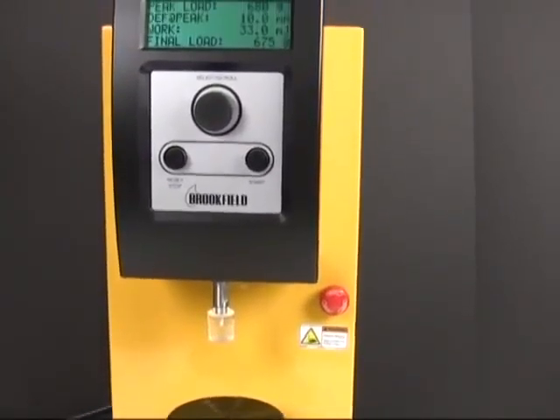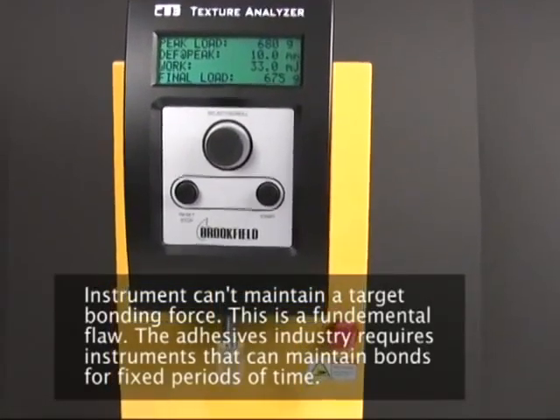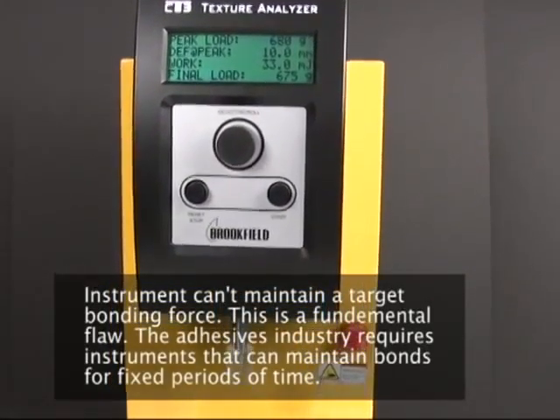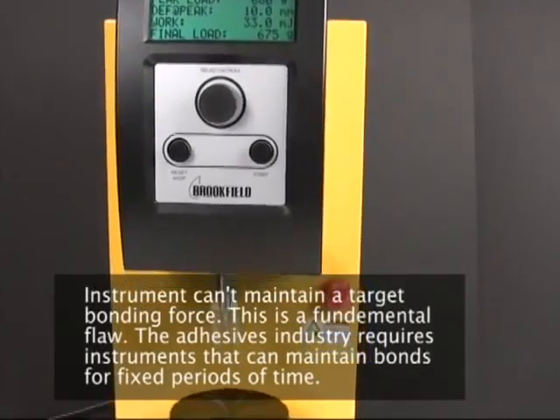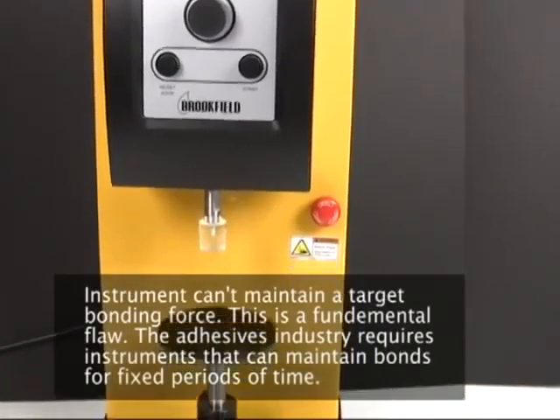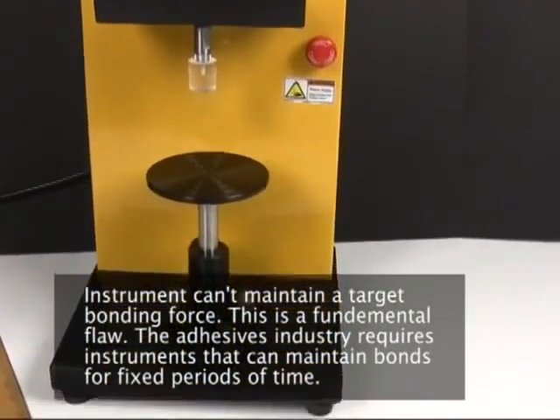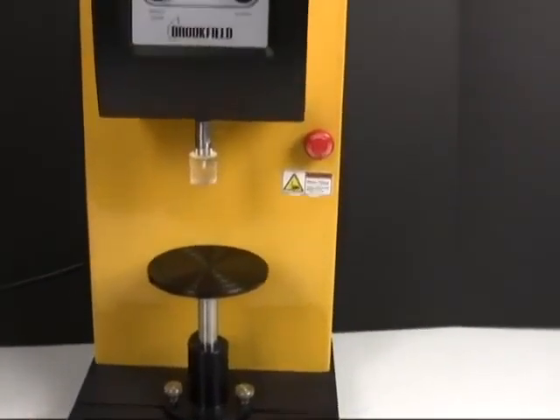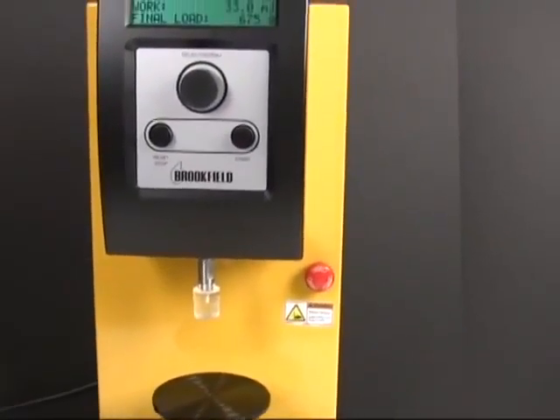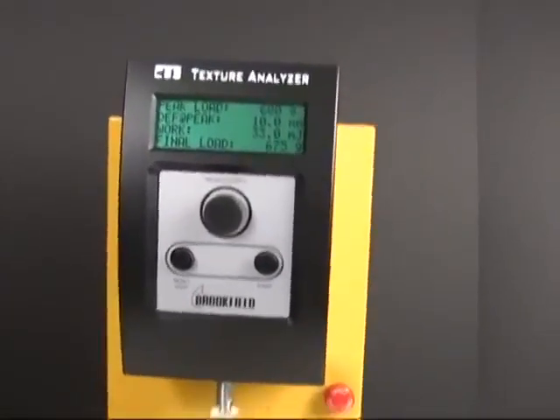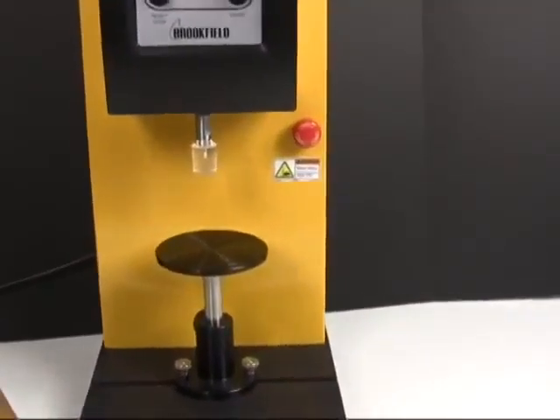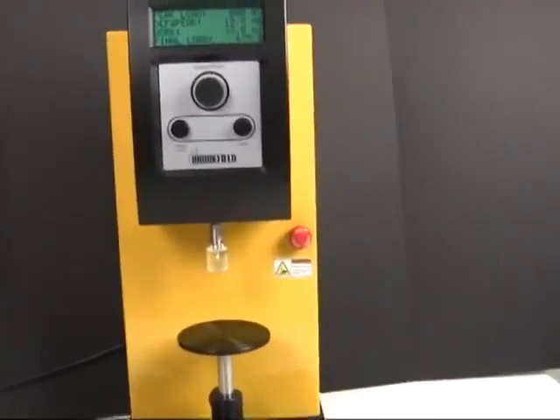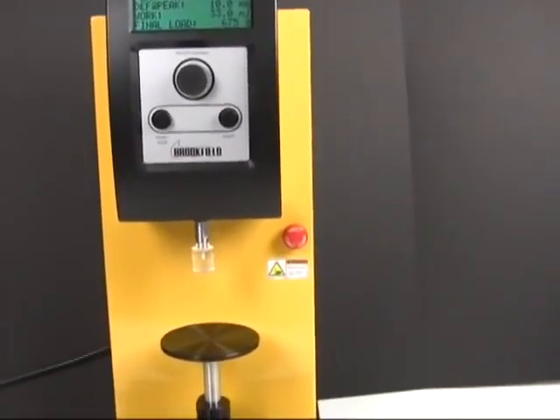or by bad I mean it can't do it, maintaining a target force. This is mainly an issue for adhesives, where you gotta maintain a bond or form a bond with the product, and it actually is to the point where this disqualifies the instrument for use in both the adhesives and medical adhesive industries. So, in summary, this is the Brookfield CT3, a pretty low-end texture analyzer.